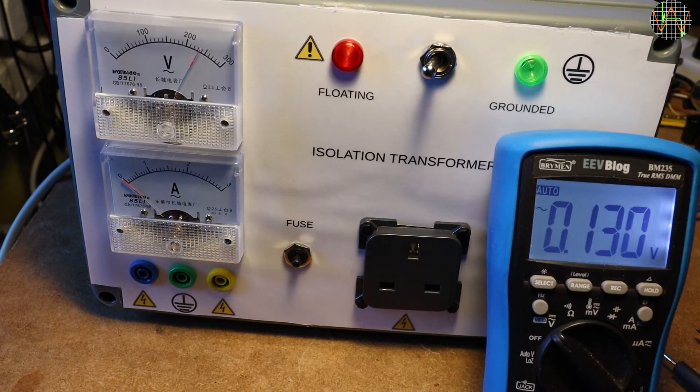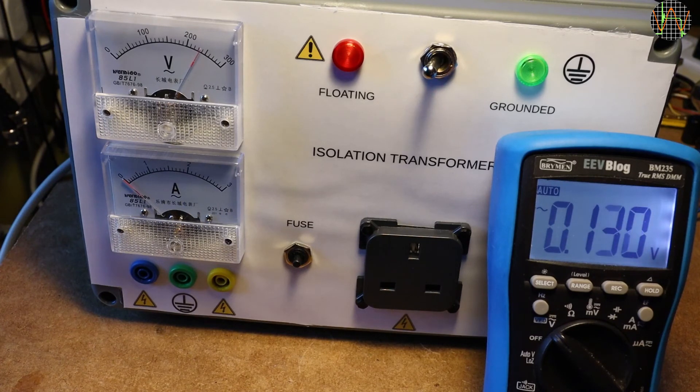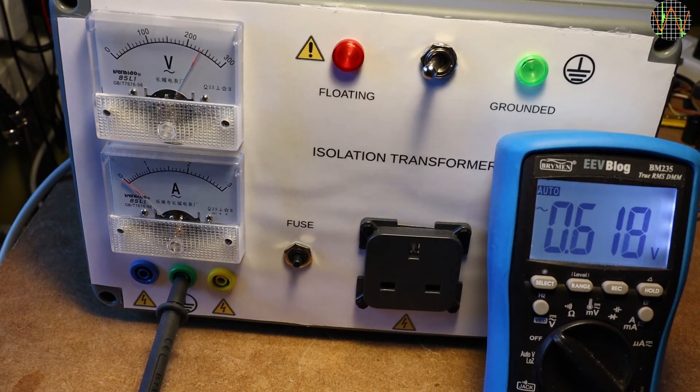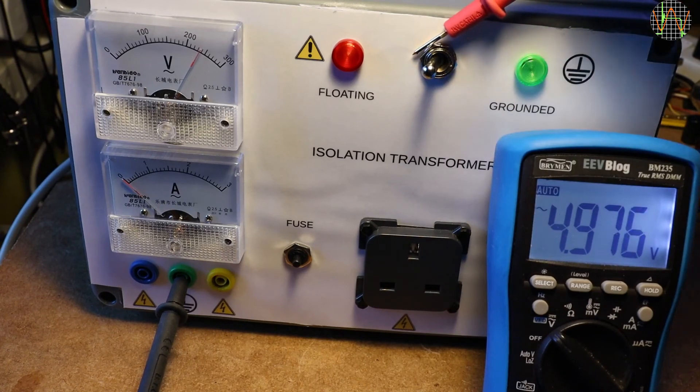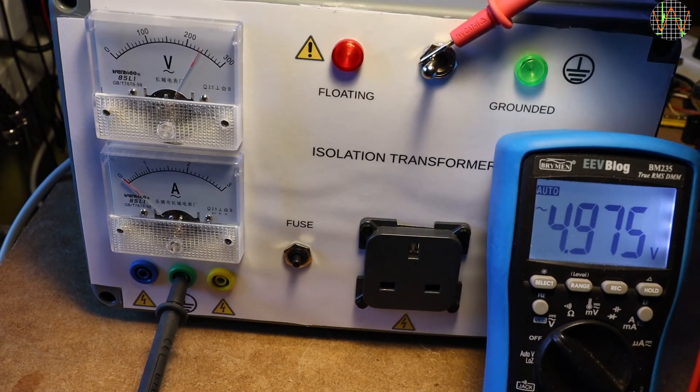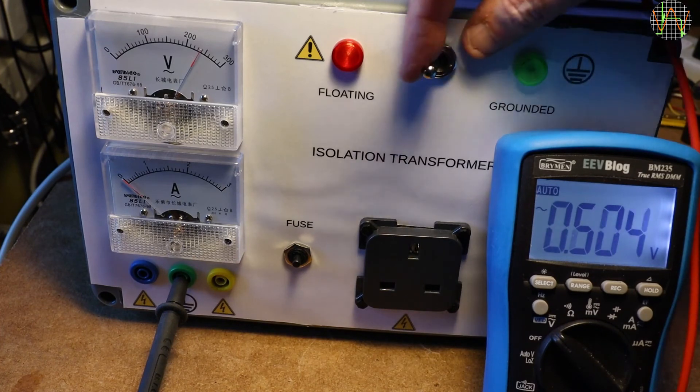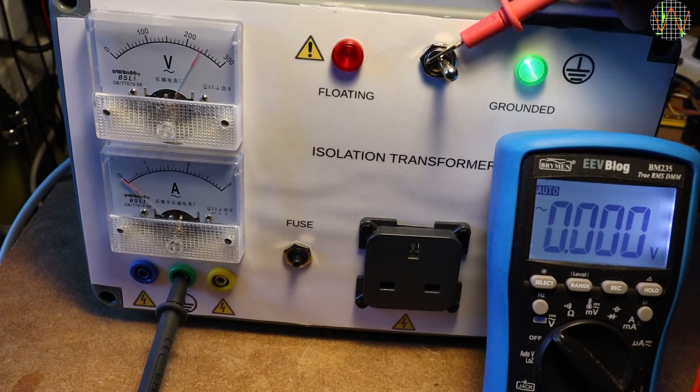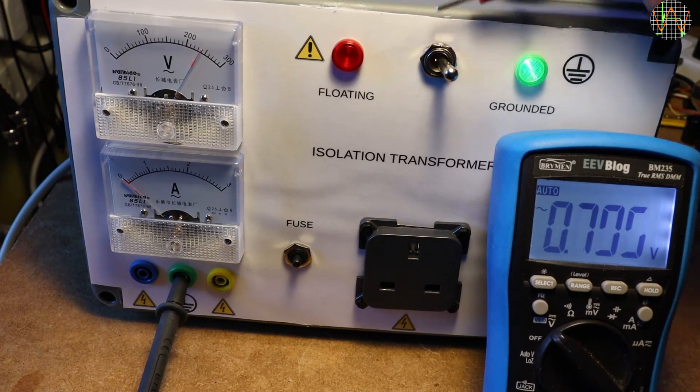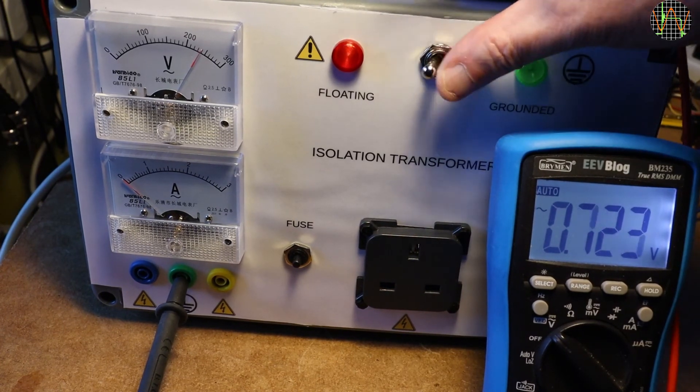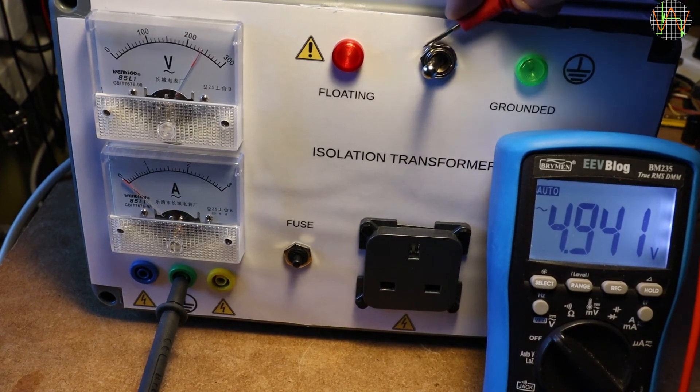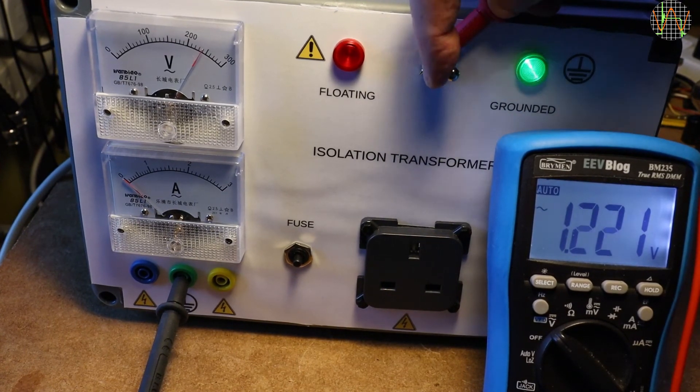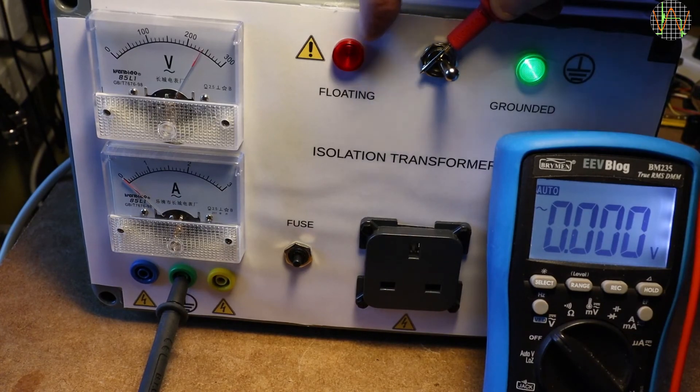With one lead in the ground terminal and the switch set to floating, you will measure some stray voltage when touching the proper ground with the other lead or in this case the metal of the switch. About 5V AC. This goes to 0 if the switch voltage is set to grounded and working properly. Let me do it again. Floating. Some non-zero voltage, for example 5V. Grounded. Zero.